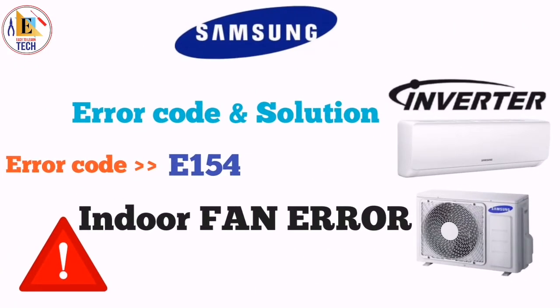When you see error code E154 on your display, it means indoor fan error. Your LED 3 will be blinking and LED 1 and LED 2 will be off. At that time you can understand it's an indoor fan error. First of all, restart your unit and check if the fan is rotating or not.